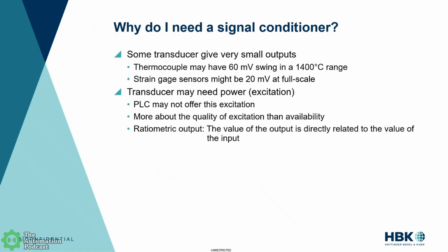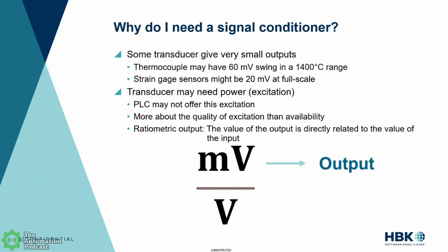strain gauge sensors operate on this idea of a ratiometric output, where the value of the output is directly related to the value of the input. Most of the time when you look at strain gauge sensors, you'll see the output listed as millivolt per volt. It's a unitless quantity, and it doesn't make a whole lot of sense until you dive into what these two elements really are. So we have our millivolts of output. I mentioned earlier, a strain gauge sensor might have 20 millivolts at full scale, divided by our voltage input, so our excitation voltage. In my example of 20 millivolt output, most HBK transducers have a datasheet sensitivity of 2 millivolt per volt, meaning that if you excite with 10 volts, you will get 20 millivolts out.